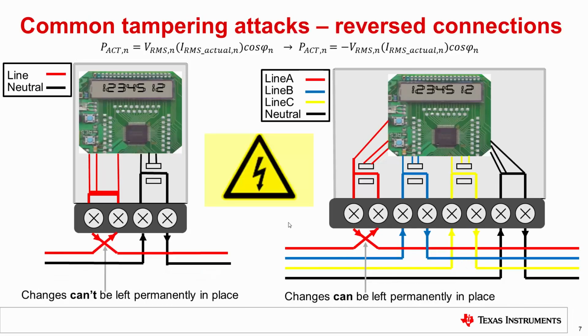Now that we went over the meter connections, let's talk about some common tampering methods. One of these common tampering methods is to reverse the connections on a meter. In the picture on the left, the line in and line out wires have been swapped. When swapping the wires, there is a risk to the tamperer because of the potentially harmful mains voltage that could shock the tamperer. The swapped line connections actually cause a negative value for active power.